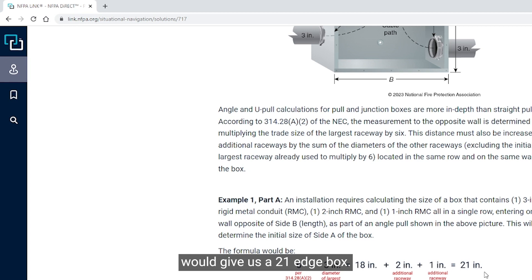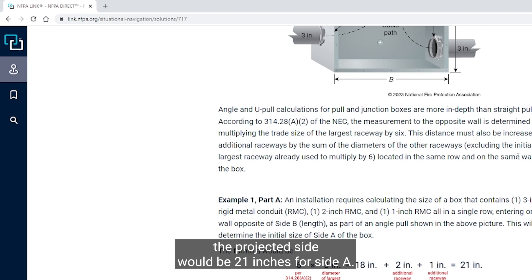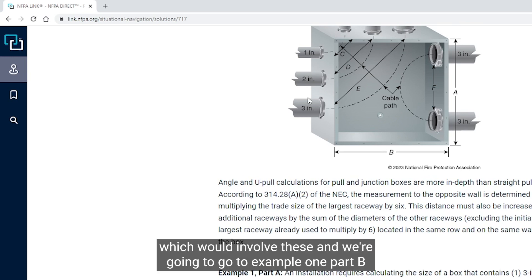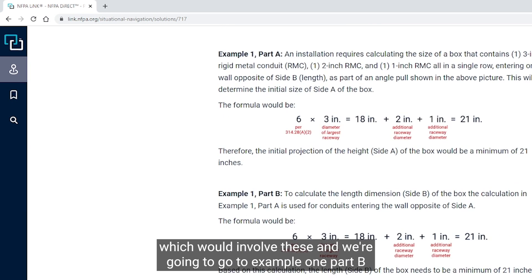So we have conduits entering in or raceways entering in opposite of B. The installation is that we have one 3-inch rigid conduit, one 2-inch rigid conduit, and one 1-inch rigid conduit all in a row entering on the same wall opposite of side B. So we are going to be solving for side A, what the length is or height.